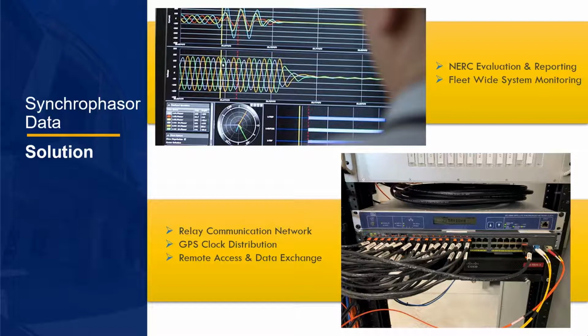To support the value-added PMU functionality and utilize the full ability of the new relays, a relay communication network was included in the project design. The new network provided GPS clock distribution and created the ability for remote access and further data exchange capabilities. To note, PMU functionality requires a high accuracy clock signal, one that is not available via Precision Time Protocol network distribution, hence why the PMU relays, the GSU relays, have IRIG-B clock connections.